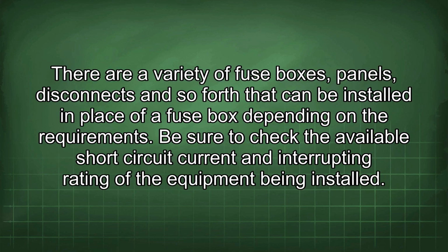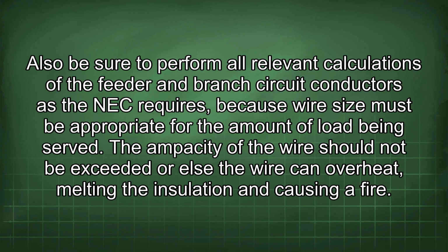There are a variety of fuse boxes, panels, disconnects and so forth that can be installed in place of a fuse box depending on the requirement. Be sure to check the available short circuit current and interrupting rating of the equipment being installed. Also be sure to perform all relevant calculations of the feeder and branch circuit conductors as the NEC requires, because wire size must be appropriate for the amount of load being served.